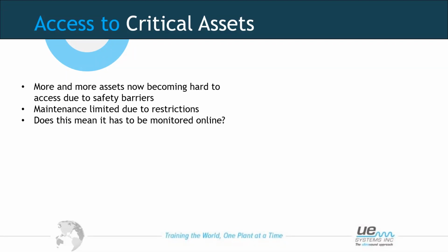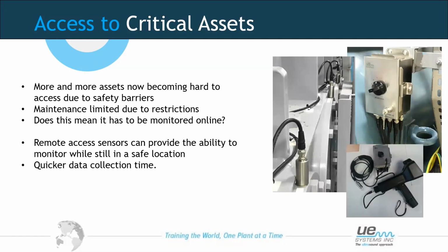So when we have our critical assets on our sites, we do see a lot more these days issues with access and people not being able to maybe get into, monitor or maintain their assets very well for these sort of predictive approaches. So does that mean we need to stick online systems on there? Not necessarily. It might be that we could look at using remote access sensors where we can wire and fit sensors remotely, running them to a distribution box where we can access and plug in our ultrasound device into the actual probe. That way, it helps us with taking our readings on areas where we cannot access and being able to collect data sometimes on a much quicker timescale.